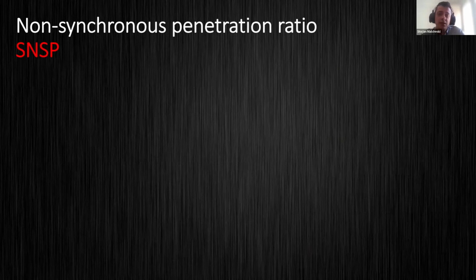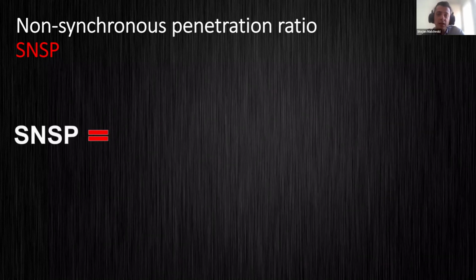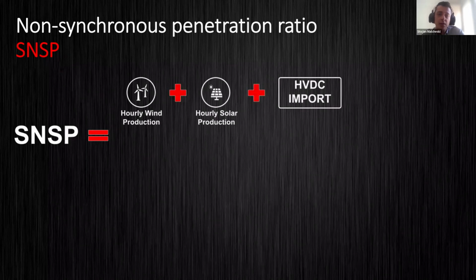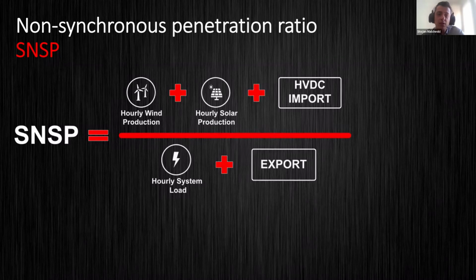The final metric is the non-synchronous penetration ratio, which is used to estimate system inertia. This metric is calculated as the hourly production of wind and solar plus the import through HVDC cables, all divided by the hourly system load and the export for that hour.